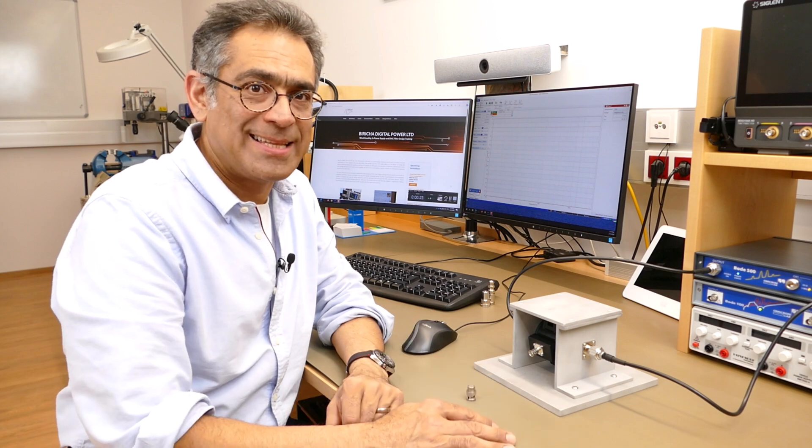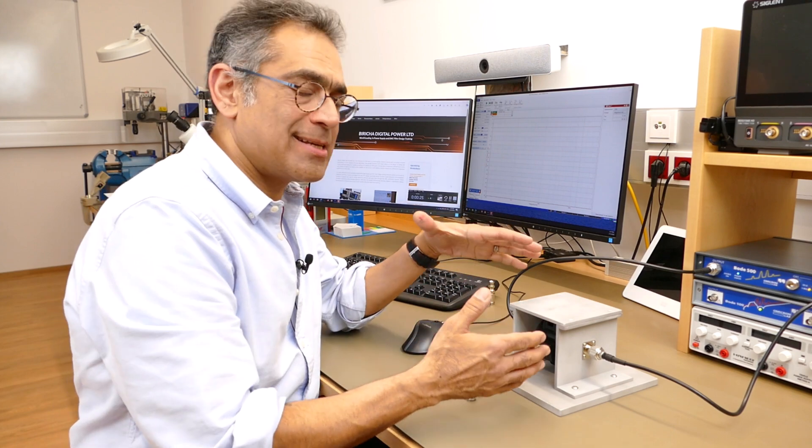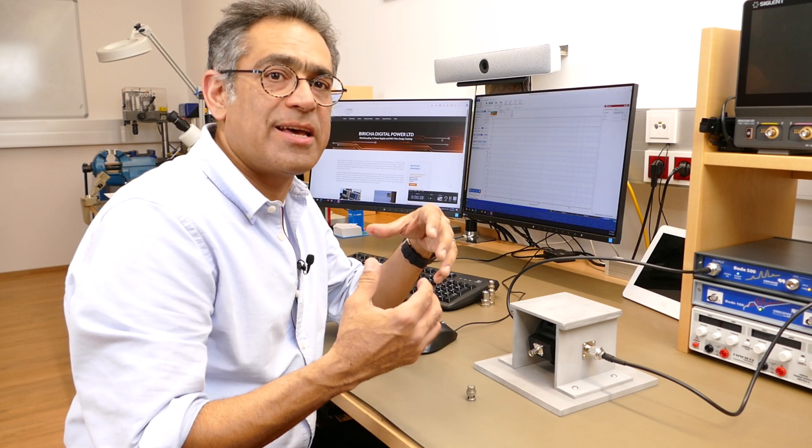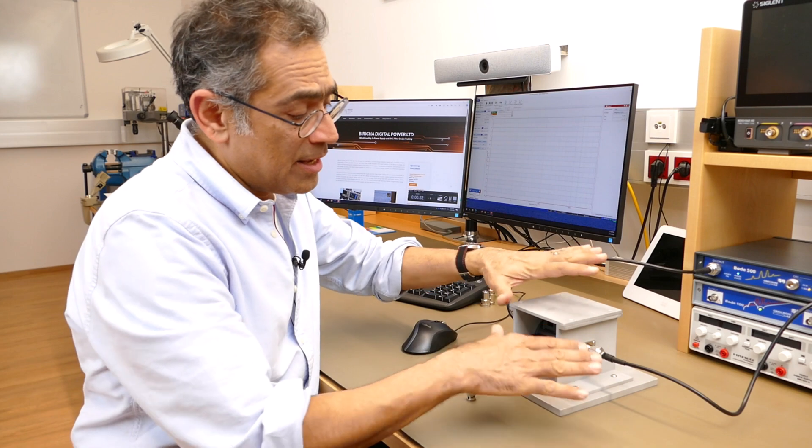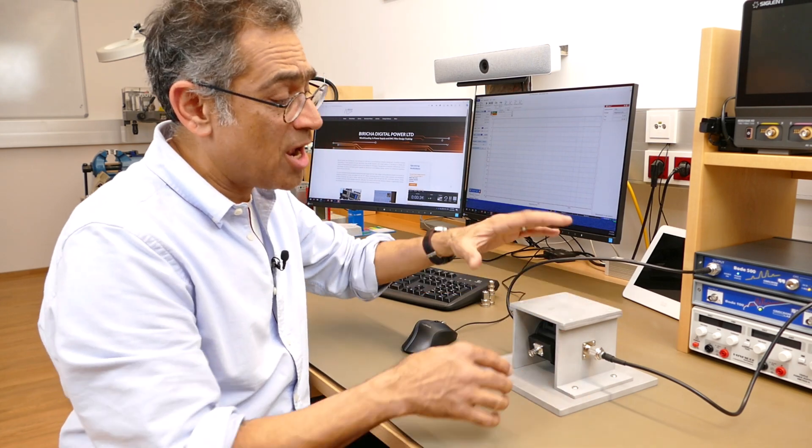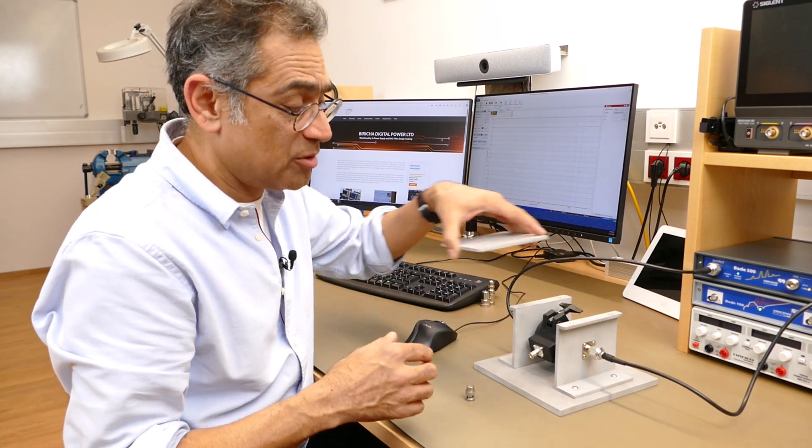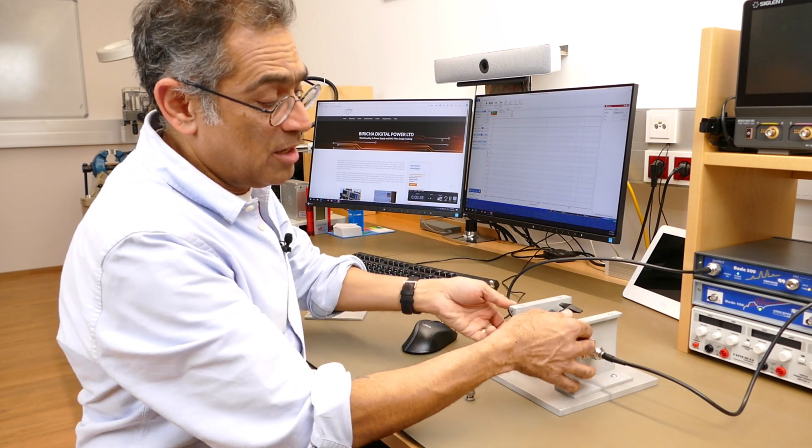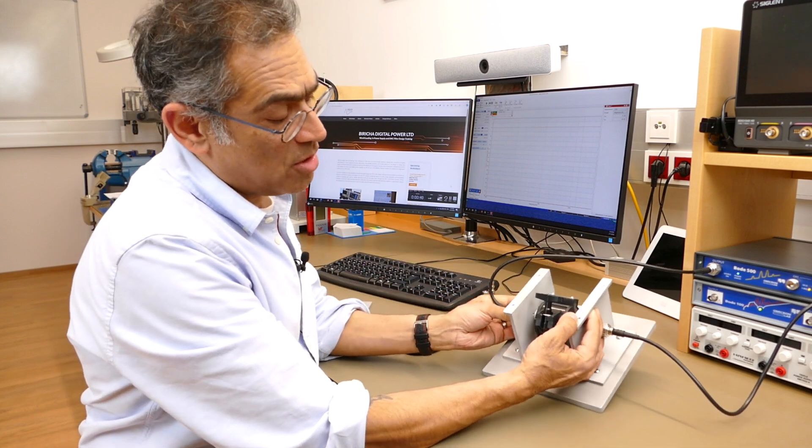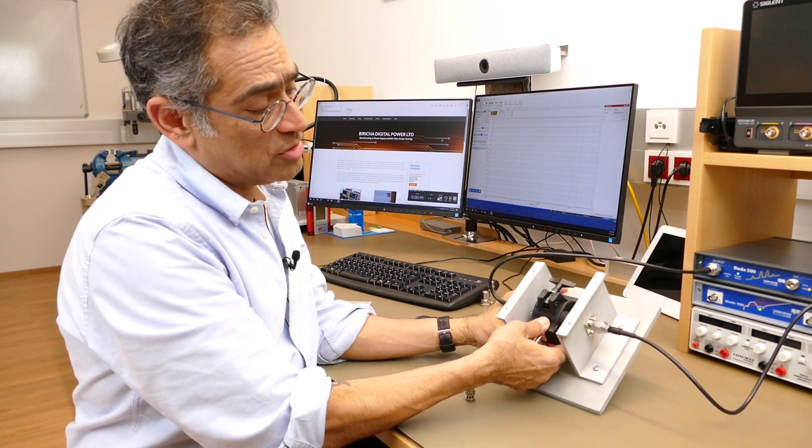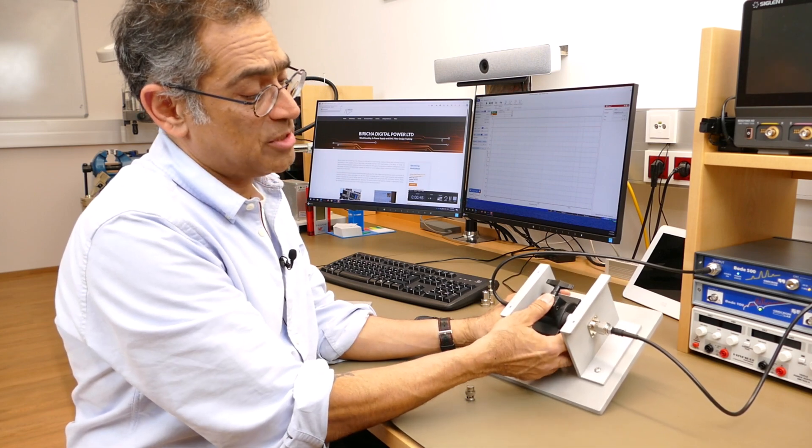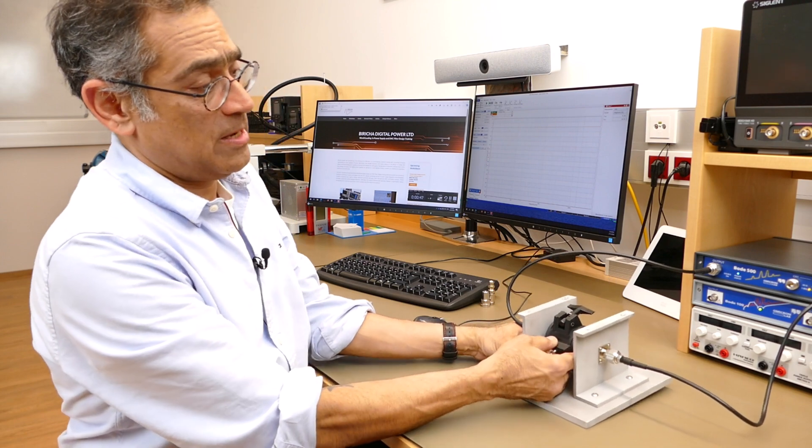So here we are in the lab, and this is the test setup that we use in order to create the transfer impedance plot that I mentioned earlier on. And here is our calibration test fixture - I've actually unscrewed the top so that we can show you what's happening in this video. In reality the top needs to be screwed on. The current clamp is going in the middle of the calibration test fixture.